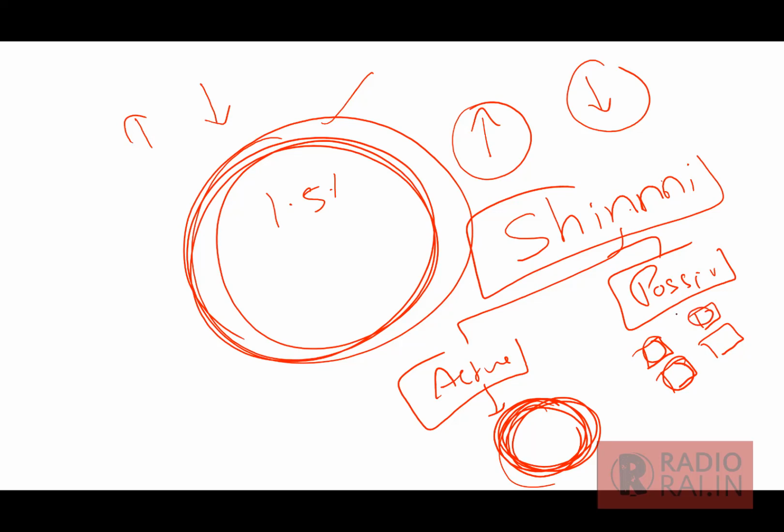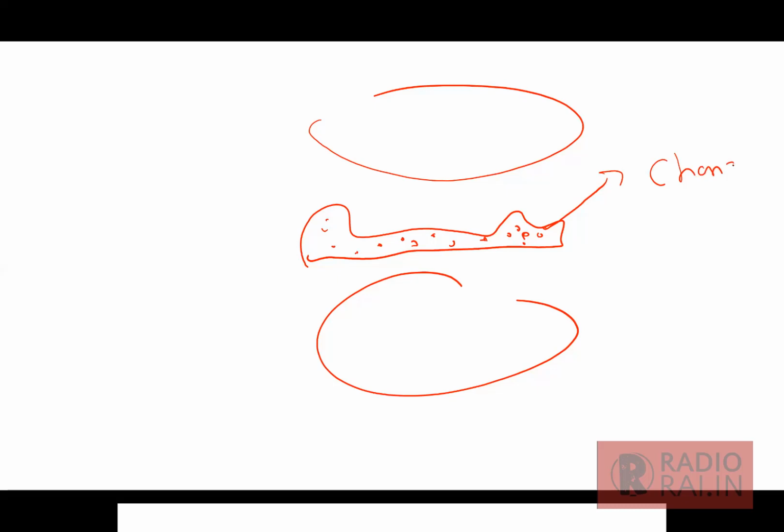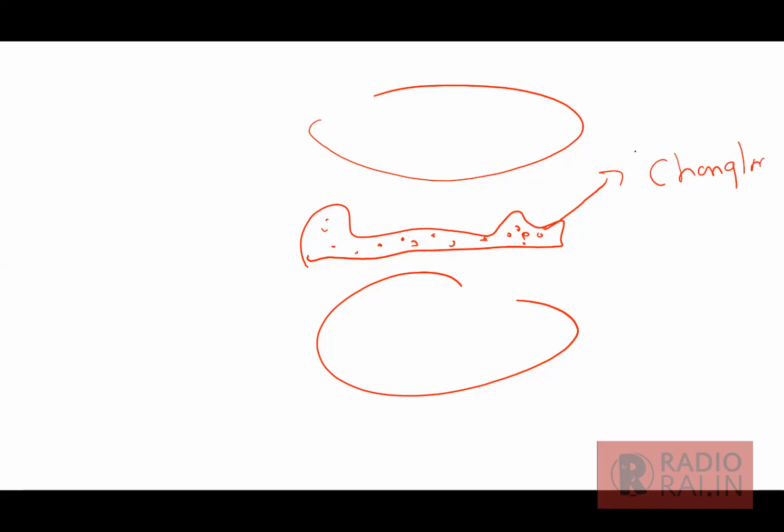Now, whenever I place a patient inside the gantry, the patient has multiple hydrogen atoms, and each hydrogen atom acts like a magnet. So even the patient is responsible for changing the magnetic field. The patient also causes some alteration in the magnetic field. This is also adjusted by the shim coils. So these shim coils are always active.